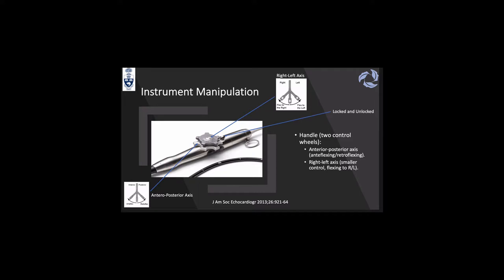For instrument manipulation, the classical probe shown here is specifically the X7 Philips probe — same principle applies to GE and Siemens machines. There are two knobs: the smaller handle on top gives you right-to-left axis movement of the probe; the larger handle underneath allows anteflexion or retroflexion. You also have the ability to lock or unlock probe movements. The GE machine has an extra knob in the middle that lets you jump from 0 to 90 degrees in angle.